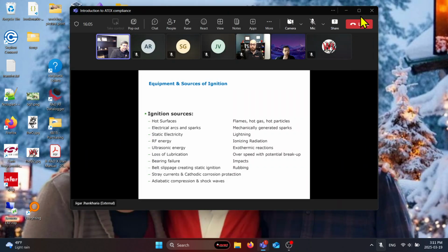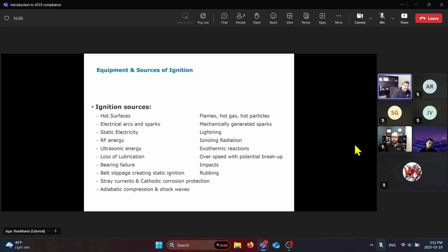Can I ask for a clarification here? Sometimes we use the term explosive, and then sometimes it's ignition. Should we be making a distinction between something exploding versus something catching on fire? They're used interchangeably, to be honest, in the market. Even when you read the standard, you'll see it says flame proof instead of explosion proof. But the meaning is pretty much the same, where an explosion proof enclosure means that the explosion is contained inside. The standard calls it flame proof, where the flame can't exit the enclosure.